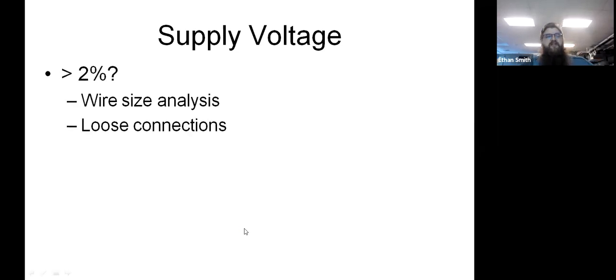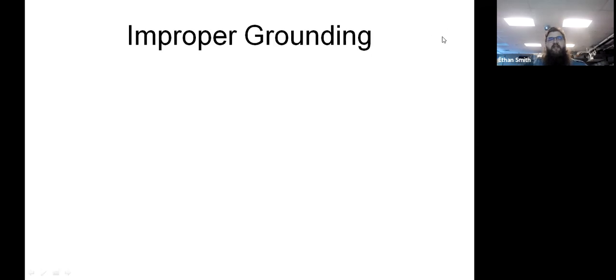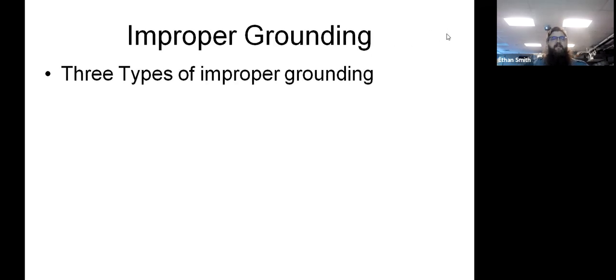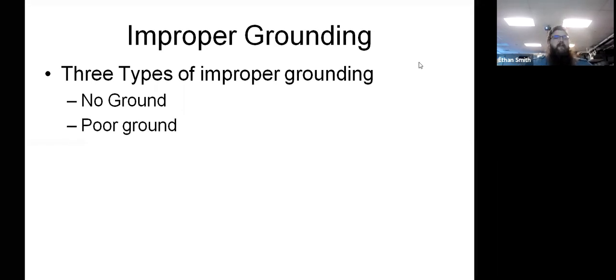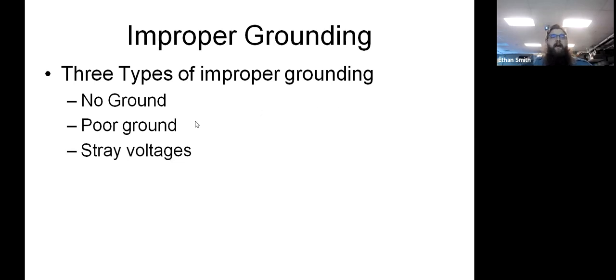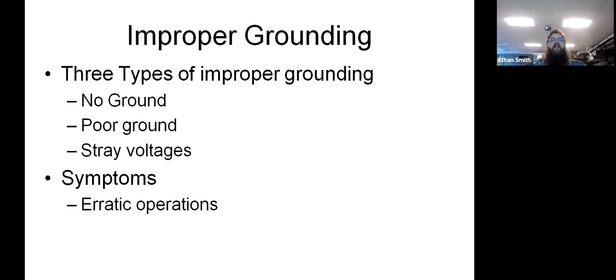Okay, so we talked about wires, loose connections, things like that. The other thing we need to address on electrical is grounding. So there's lots of improper grounding out there. There's the no ground situation, in which case anybody who touches it becomes ground. You've got a poor ground, meaning stuff's loose. It's not got enough grounding rod in the service. Or you can have stray voltages. This happens with frequency drives, high capacity motors. Rotating magnetic fields will generate stray voltages. A lot of the symptoms, especially in the furnace and air handler market, is you will get very erratic operation. Many of these units suffer from what we affectionately refer to as random error syndrome if there's no ground, especially the furnaces.